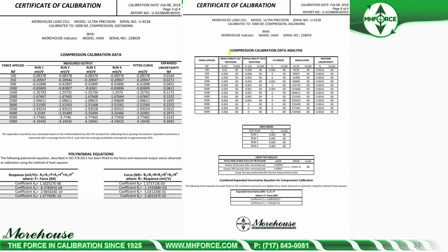And then page 4 of the CERT has all the classes. If you look through here, you can see repeatability with rotation. Here's all class 00, repeatability without rotation, fit error, resolution. It tests for resolution, uncertainty of the machine, class 0, zero error down here, all 00s, creep, all 00s. And then an expanded uncertainty equation is reported, which is nice. So you can use this equation for the expanded uncertainty at any point during the force range, and it will tell you what your actual uncertainty is.